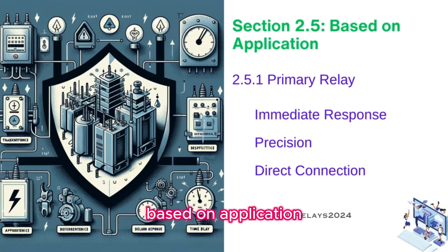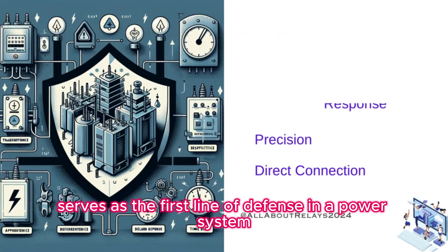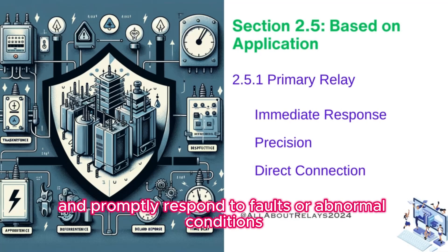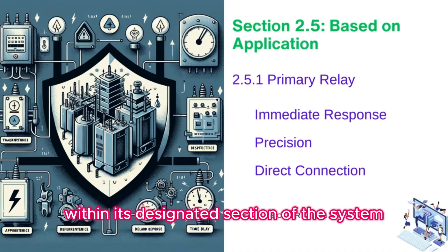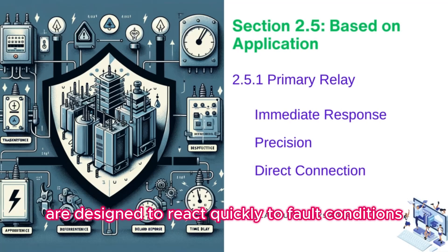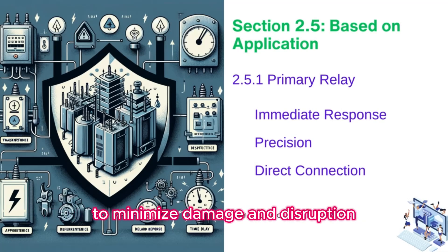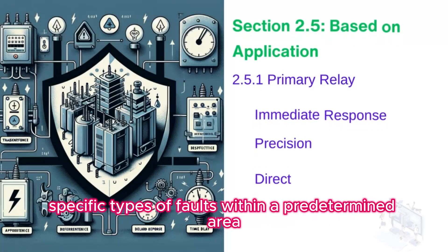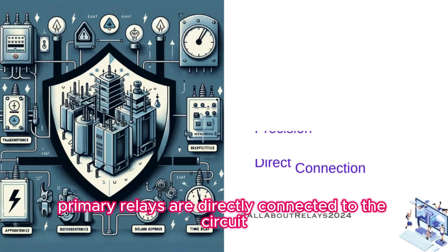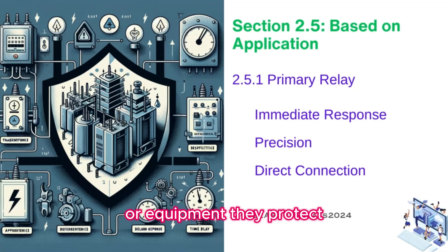Protective relay types based on application. The primary relay, often referred to as the main relay, serves as the first line of defense in a power system protection scheme. Its principal function is to detect and promptly respond to faults or abnormal conditions within its designated section. Primary relays are designed to react quickly to fault conditions to minimize damage and disruption. They are calibrated to detect specific types of faults within a predetermined area, and are typically directly connected to the circuit or equipment they protect, such as transformers, feeders, or generators.